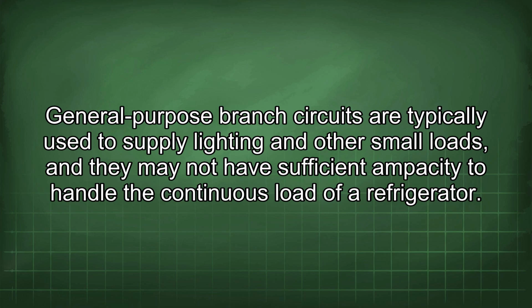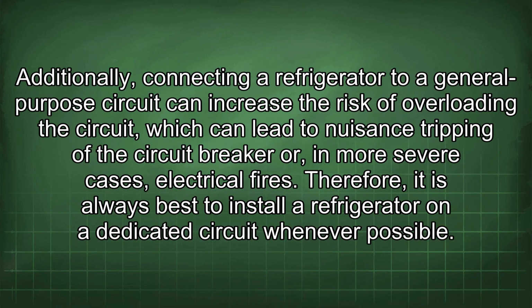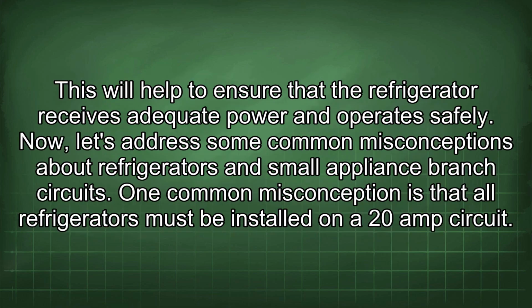General-purpose branch circuits are typically used to supply lighting and other small loads, and they may not have sufficient ampacity to handle the continuous load of a refrigerator. Additionally, connecting a refrigerator to a general-purpose circuit can increase the risk of overloading the circuit, which can lead to nuisance tripping of the circuit breaker or, in more severe cases, electrical fires. Therefore, it is always best to install a refrigerator on a dedicated circuit whenever possible. This will help to ensure that the refrigerator receives adequate power and operates safely.